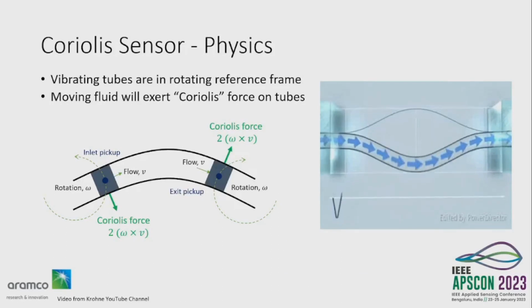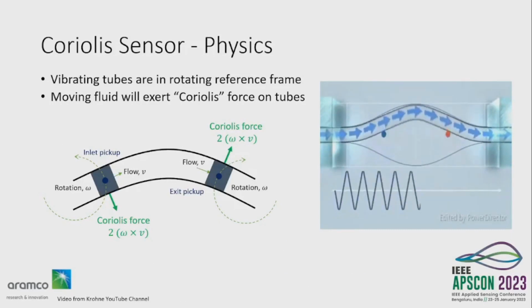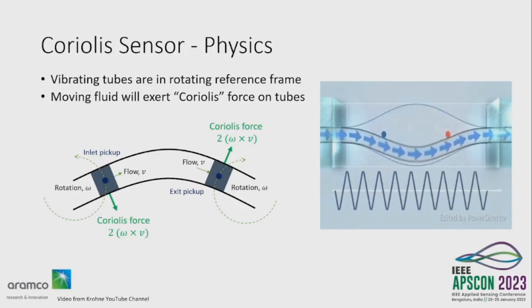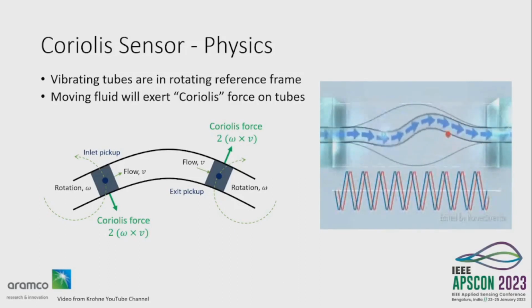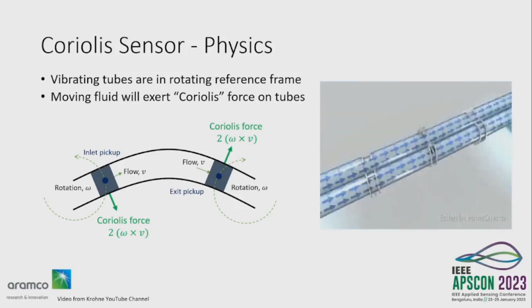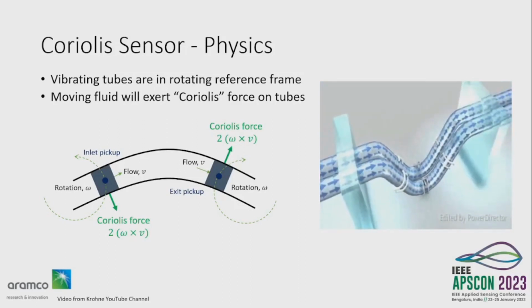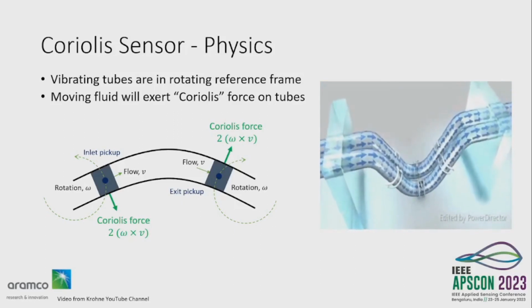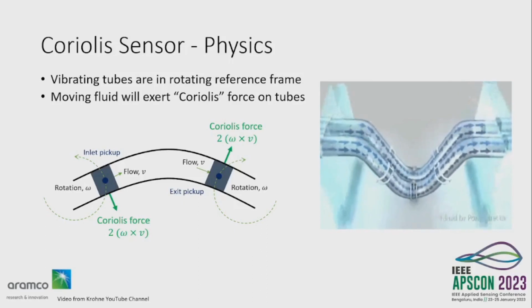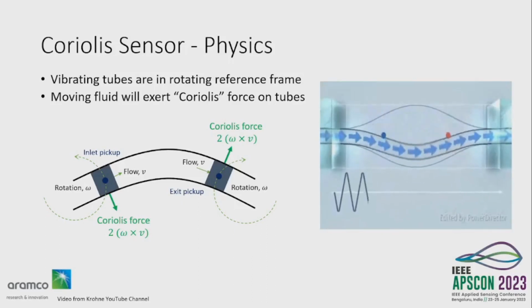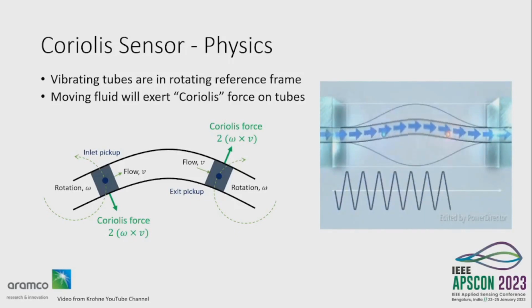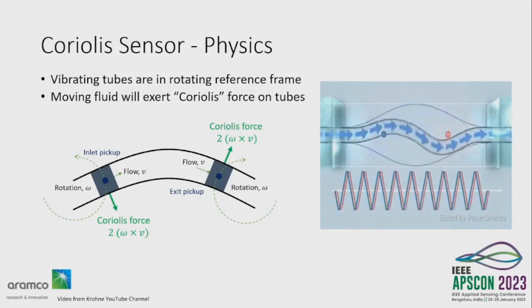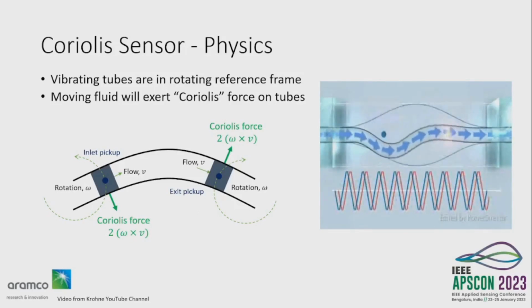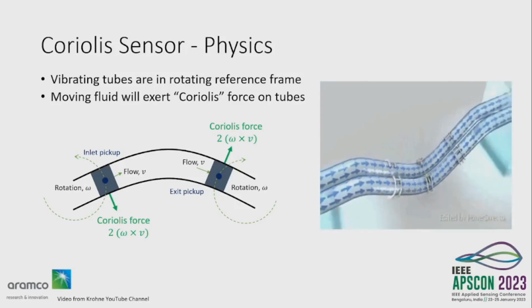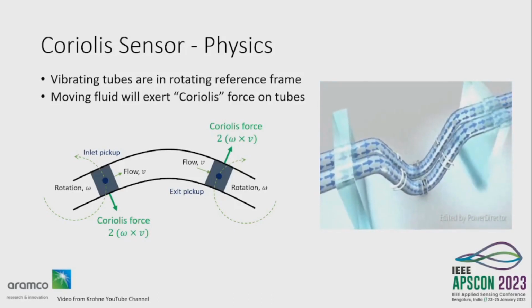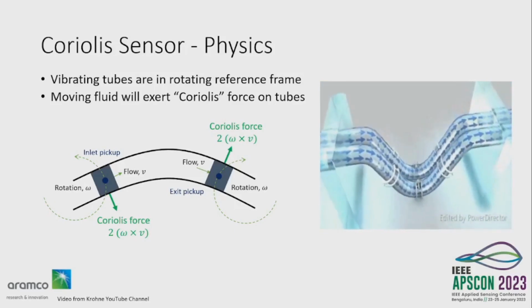So it's probably better to see. If the fluid is not moving, you can see the arrows are not moving. The resonant frequency is proportional to density. But as the flow of the fluid starts to happen, what you will see is there is a phase shift. It flows like a snake. Traditionally, a Coriolis flow sensor will have two tubes because it acts like a tuning fork. As soon as the flow starts to go, it moves like a snake, and that snake-like movement is caused by the Coriolis force, and that causes a phase shift. Right now, when there's no movement, the two sinusoidal waves are in phase, but once it starts to flow, there is a phase shift between the inlet and the outlet side. So this is how a Coriolis flow sensor works.